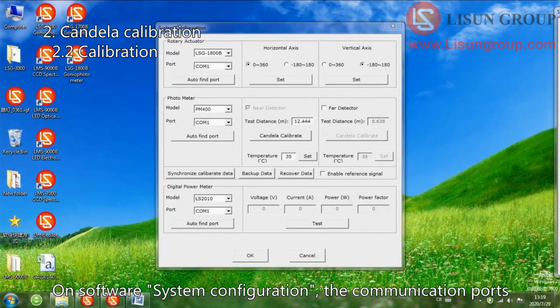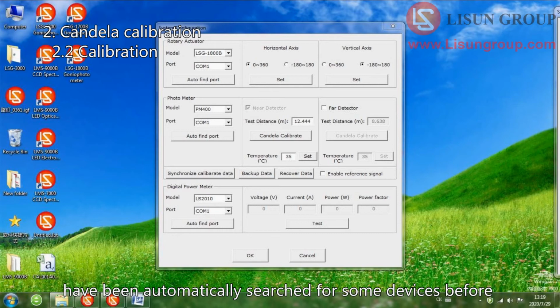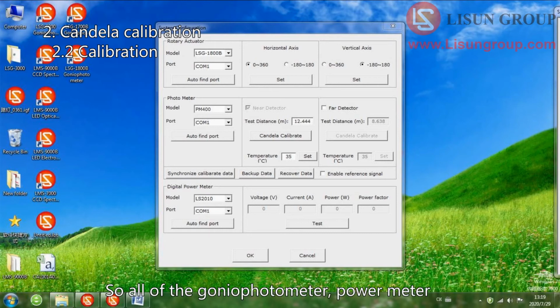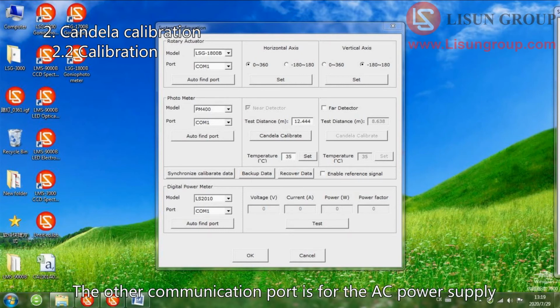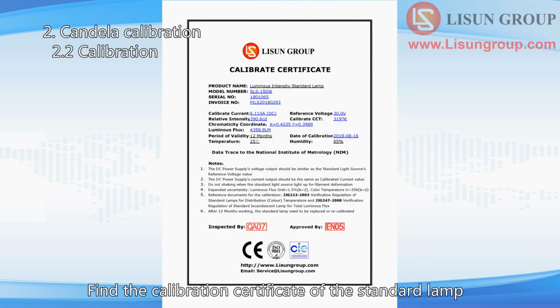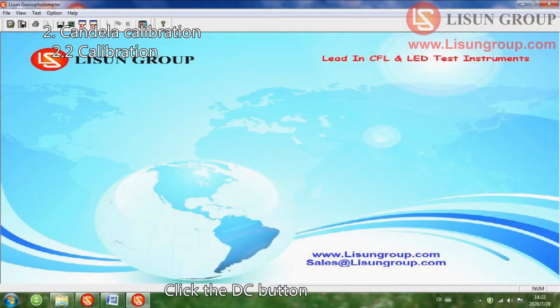On software system configuration, the communication ports have been automatically searched for some devices before. So all of the goniophotometer, power meter, and DC power supply use this port. The other communication port is for the AC power supply. Find the calibration certificate of the standard lamp. We need the data for calibration. Click the DC button.